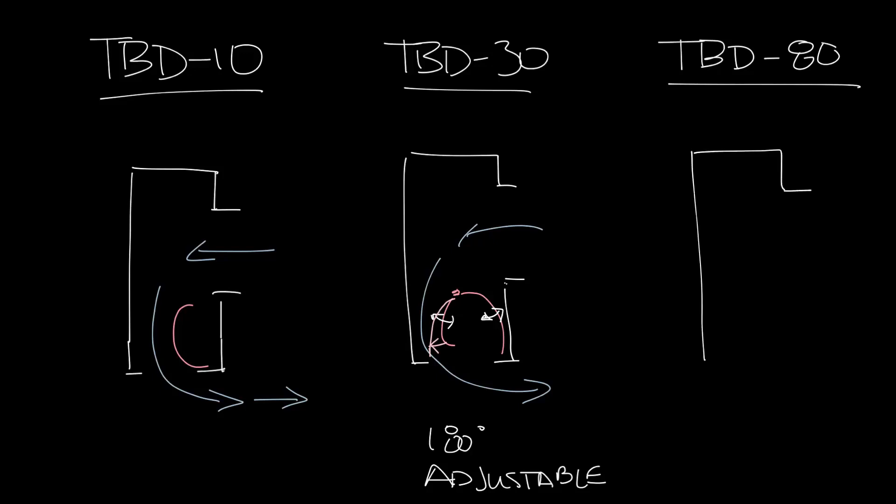The TBD-80 is somewhere in between performance-wise. It looks like this with the straight blade that has a gasket up here. The airflow would come in and go like this. This blade is adjustable. It pivots here to change your airflow pattern. It provides a 180 degree airflow pattern adjustment as well, but not the ability to damper the airflow like the TBD-30 does.